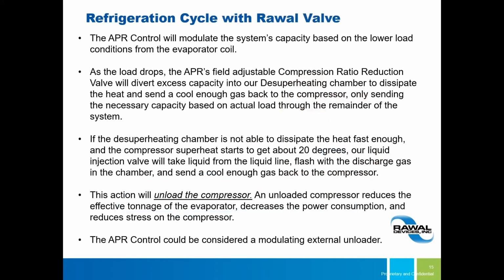But yeah, the idea is it allows you to modulate the system capacity under lower load conditions. So when the load drops, your compression ratio valve can be adjusted so you can divert whatever capacity into that desuperheating chamber that's shown in the big blow up picture. So you can dissipate the heat and send cool gas back to the compressor, only sending whatever capacity you need based on the load to the remainder of the system.